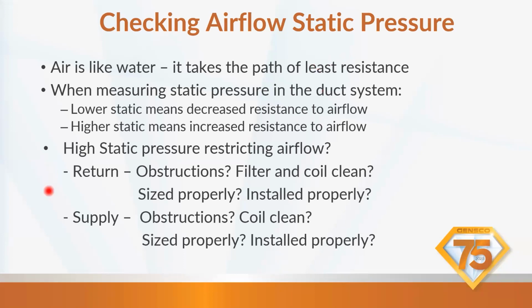Checking airflow static pressure. Again, air is like water. It takes the path of least resistance. When measuring static pressure in the duct system, lower static means decreased resistance to airflow. Higher static means increased resistance to airflow. High static pressure restricting airflow could be your return obstructions, a filter that's plugged, or a coil that needs to be cleaned. Is the ductwork sized properly? We see this a lot in retrofits, the return air ductwork not being sized big enough.